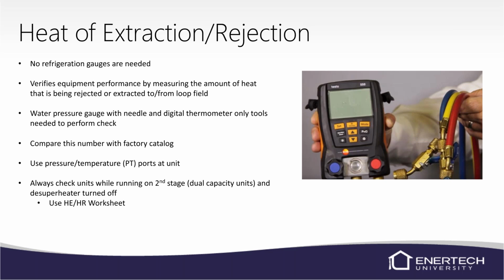Basically, you'll need a water pressure gauge. I like to use a digital pressure gauge because sometimes we get into smaller units, little half-ton units that have maybe a small pressure drop, and it's kind of hard to read on an analog gauge. So we offer a Dwyer gauge. You can purchase it from us. You can also go online. Originally, when I purchased mine, that's what I did. I went online and bought it. Make sure when you buy that gauge, or any gauge, you get the needle for it as well, because they normally don't come with the needle. I would recommend getting the thinner needle, not the real thick one, because it'll insert into those pressure temperature ports a lot better.